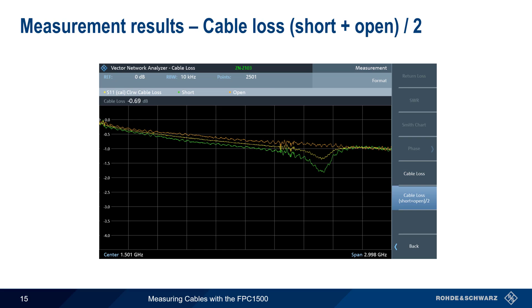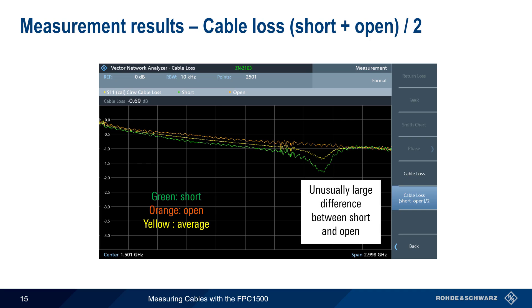When we measure using both short and open terminations, the result is three traces. Green is the measurement made with the short. Orange is the measurement made with the open. And yellow is the average of these two measurements. Here we see an unusually large difference between the open and short traces from about 2.5 to 2.7 GHz, which likely indicates a poor quality short. The result should be very similar if a high quality short is used.